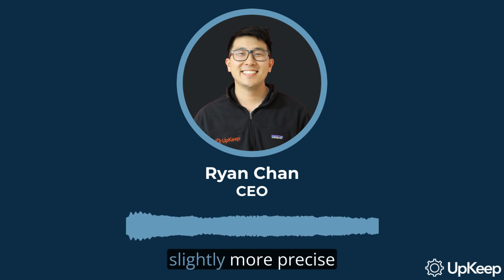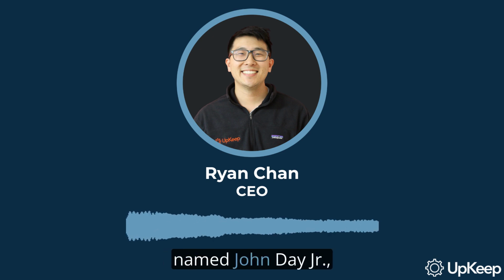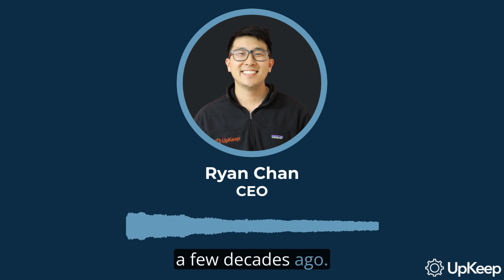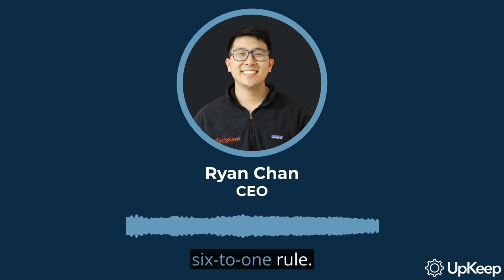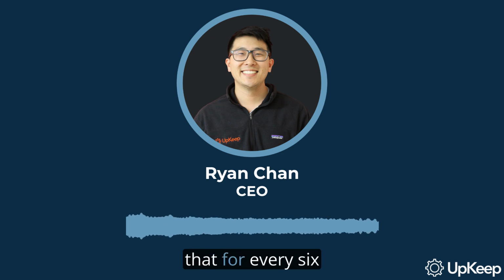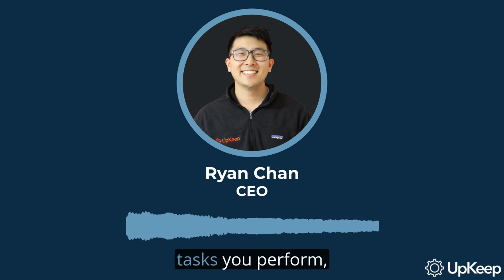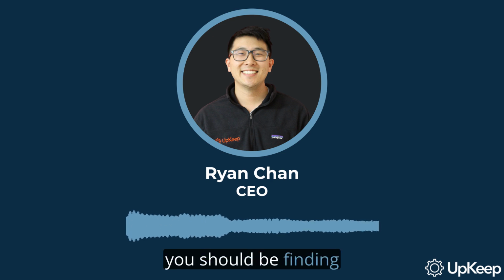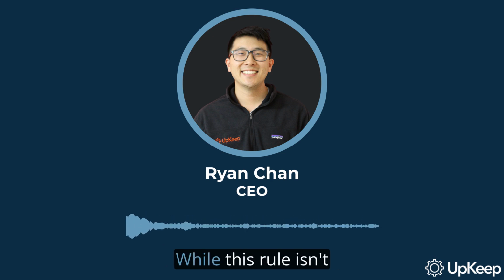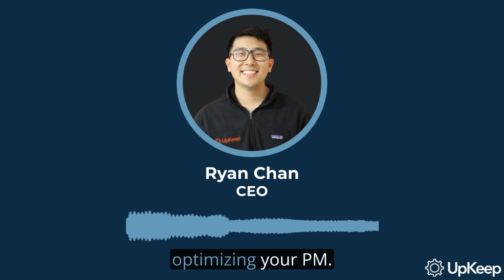Now let's talk about a slightly more precise method. This one is based on an industry assumption proposed by a maintenance and engineering manager named John Day, Jr. a few decades ago. He proposed what's known as the 6-to-1 rule. This rule suggests that for every 6 preventive maintenance tasks you perform, you should be finding 1 corrective maintenance task. While this rule isn't flawless, it can offer a good starting point for optimizing your PM.